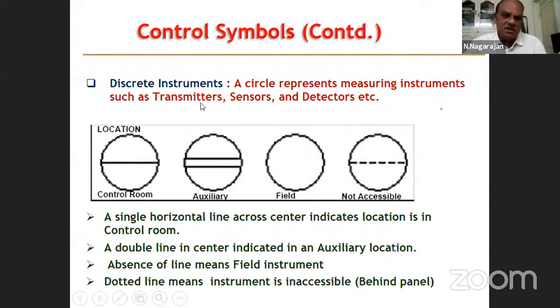For the discrete instruments, a circle represents measuring instruments such as transmitters, sensors, and detectors. If the circle has a line in the center, the location is the control room. When there is another auxiliary parameter, double lines will be shown. And a simple circle with no line means this is a field instrument. A simple circle with a dotted line is not accessible. Usually such instrumentation will be at the backside of the control panel.